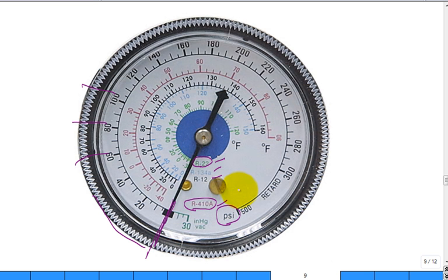There's a lot of information on this. So what they're doing is, let's do this one. If I come over and the pressure's at 60 psi, that needle lines up like this. If I'm working with refrigerant 410A, I can tell you the saturation temperature is 10 degrees. 10 degrees. And that's in what units? It's in F. Makes sense?